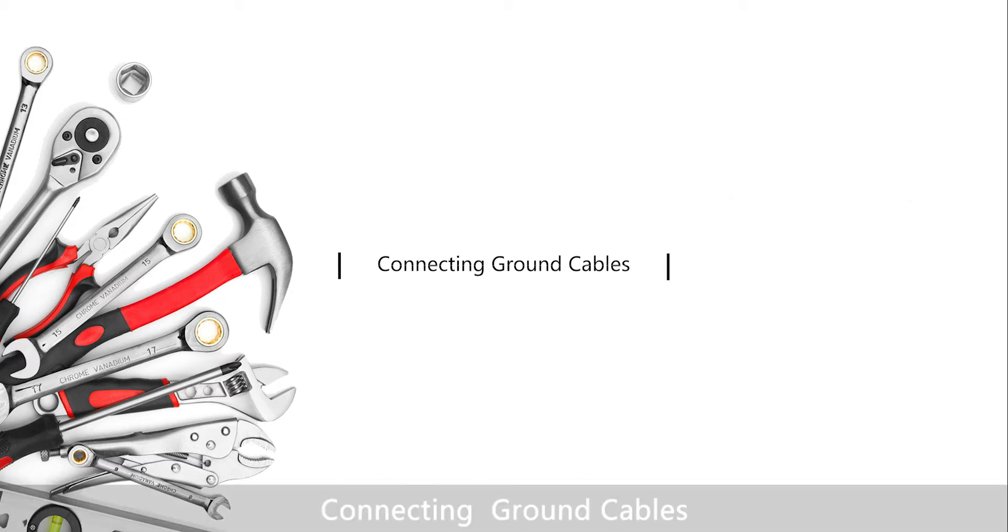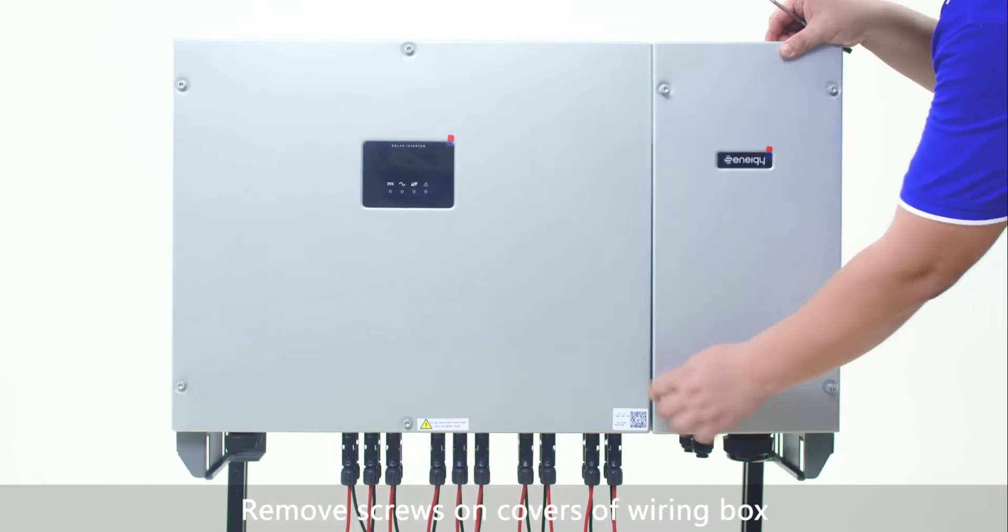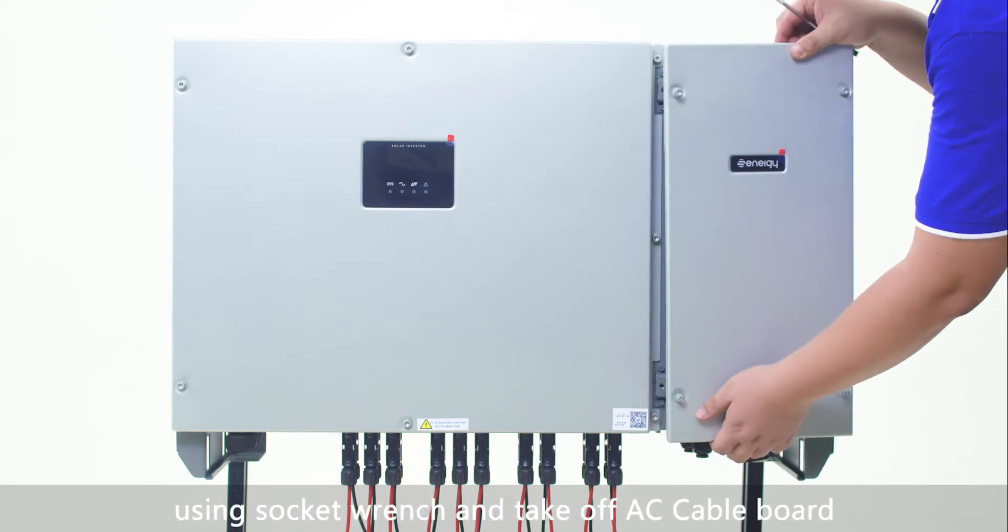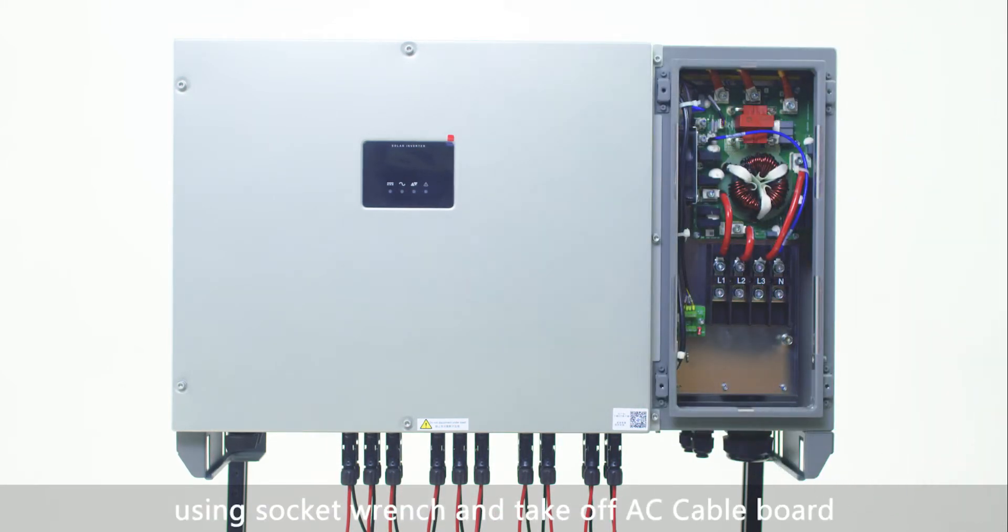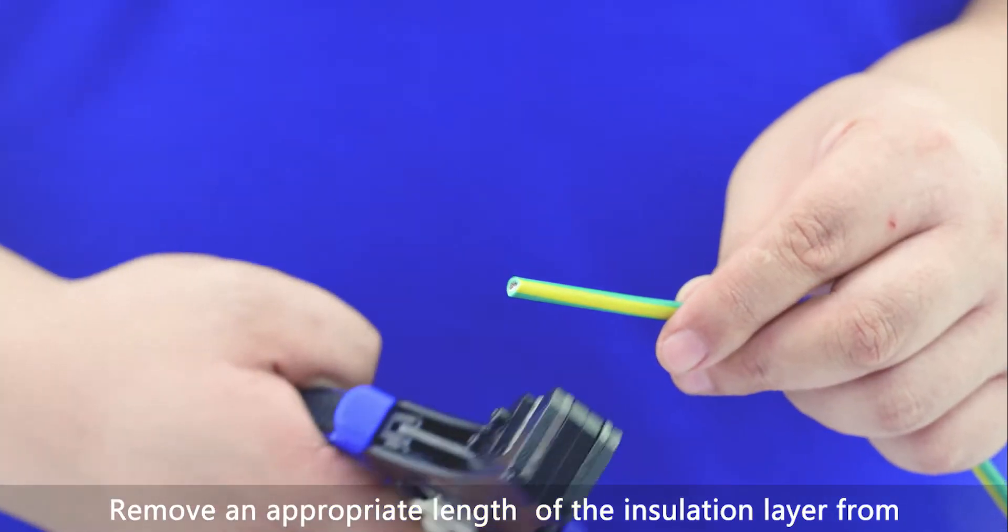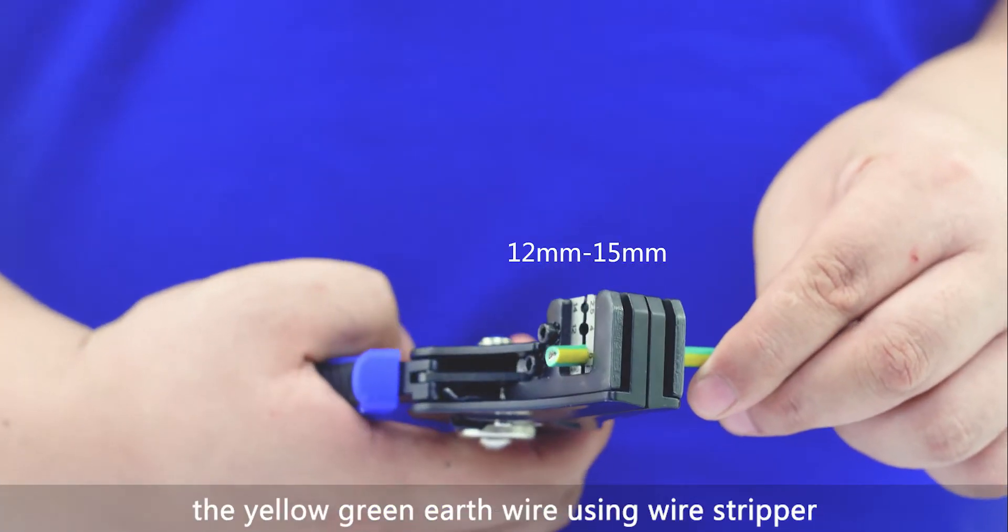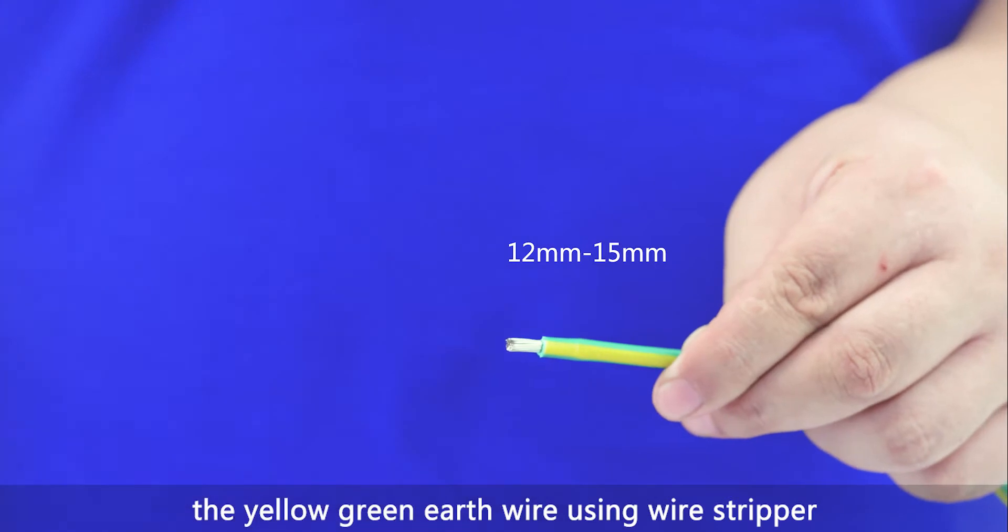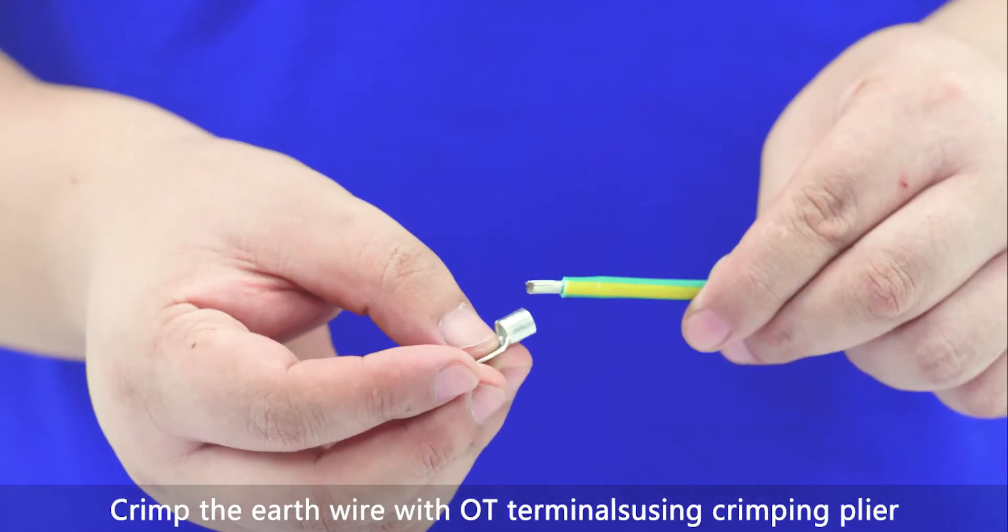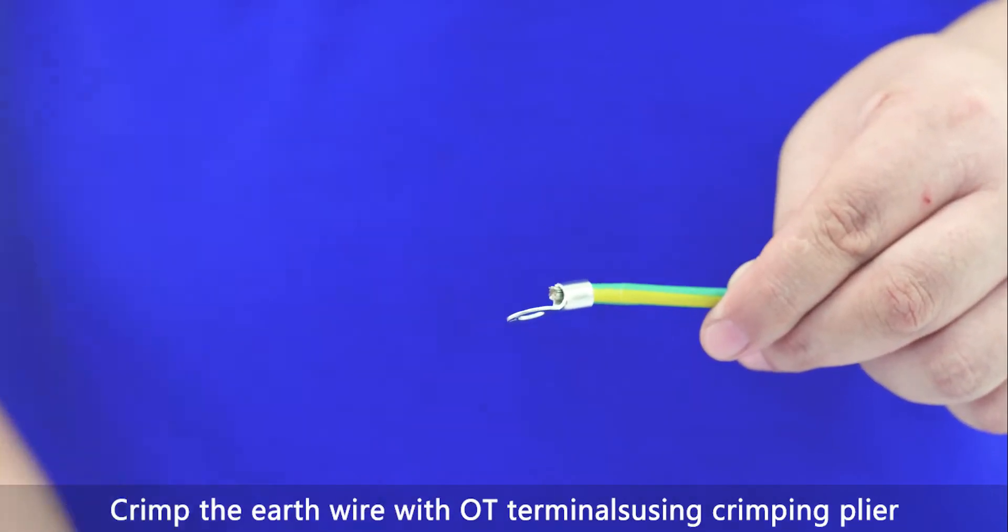Connecting ground cables. Remove screws on covers of wiring box using socket wrench and take off AC cable board. Remove an appropriate length of the insulation layer from the yellow-green earth wire using wire stripper. Crimp the earth wire with OT terminals using crimping plier.